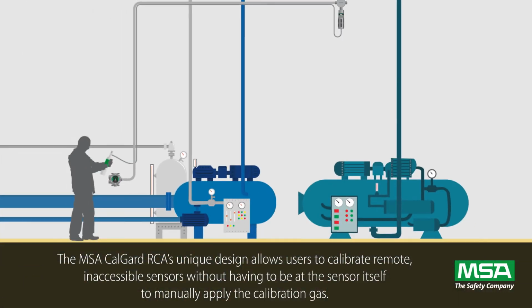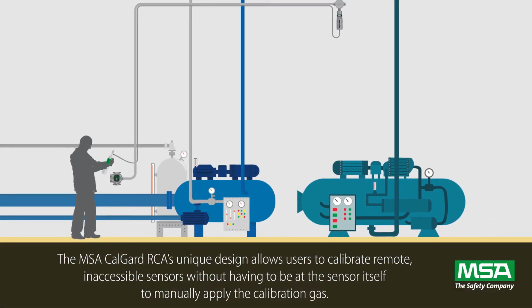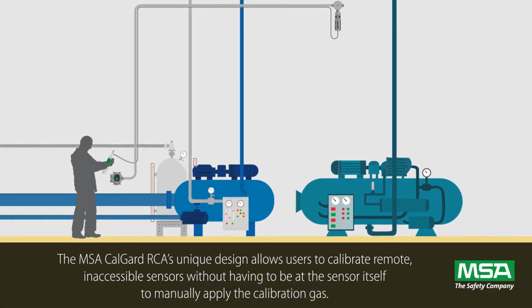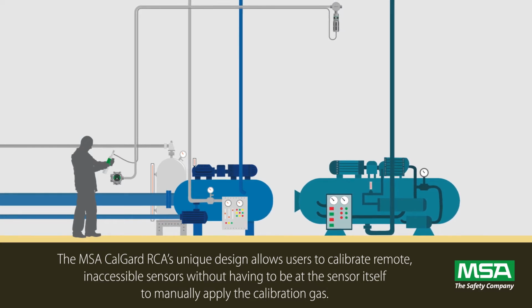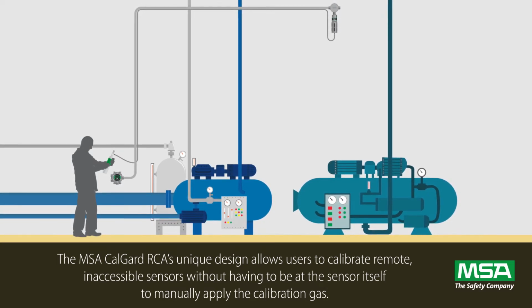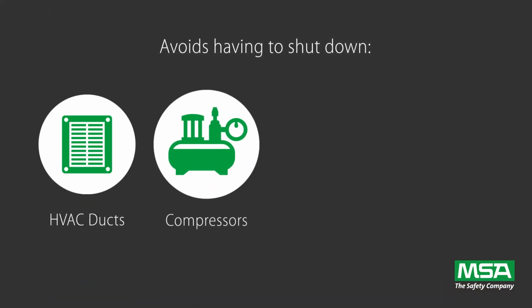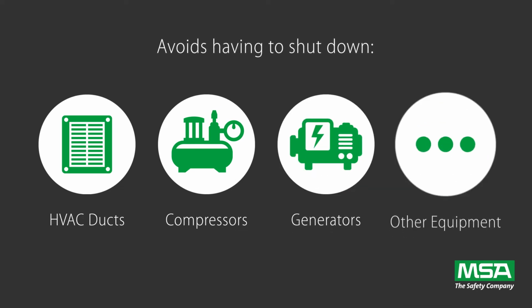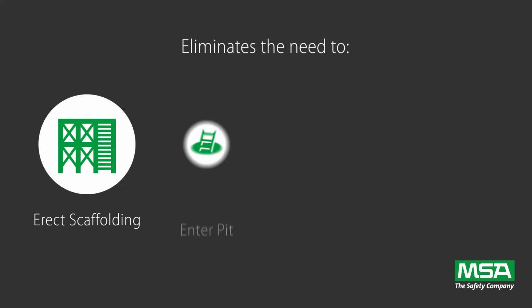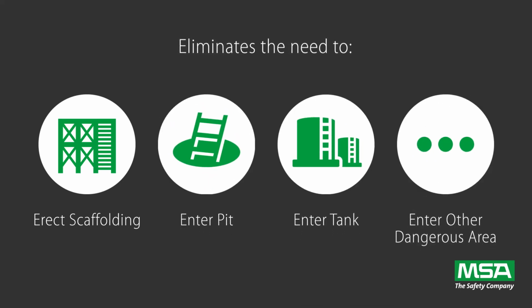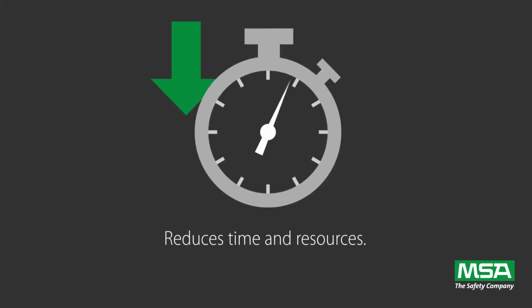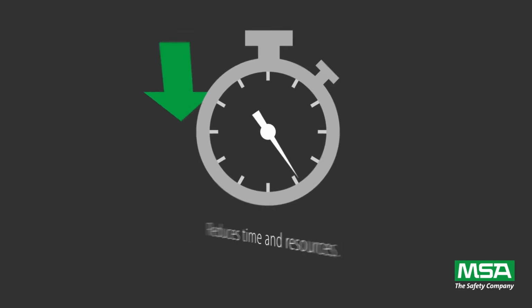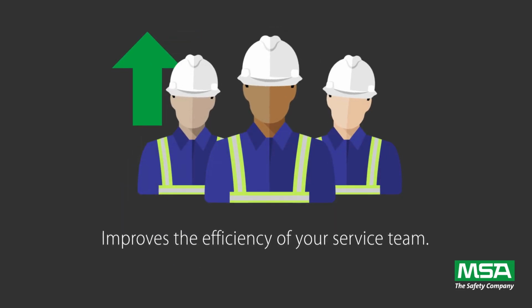The MSA CalGard RCA's unique design allows users to calibrate remote, inaccessible sensors without having to be at the sensor itself to manually apply the calibration gas. This avoids having to shut down HVAC ducts, compressors, generators, or any other equipment, and eliminates the need to erect scaffolding or enter a pit, tank, or similar dangerous areas. It also reduces time and resources and improves the efficiency of your service team.